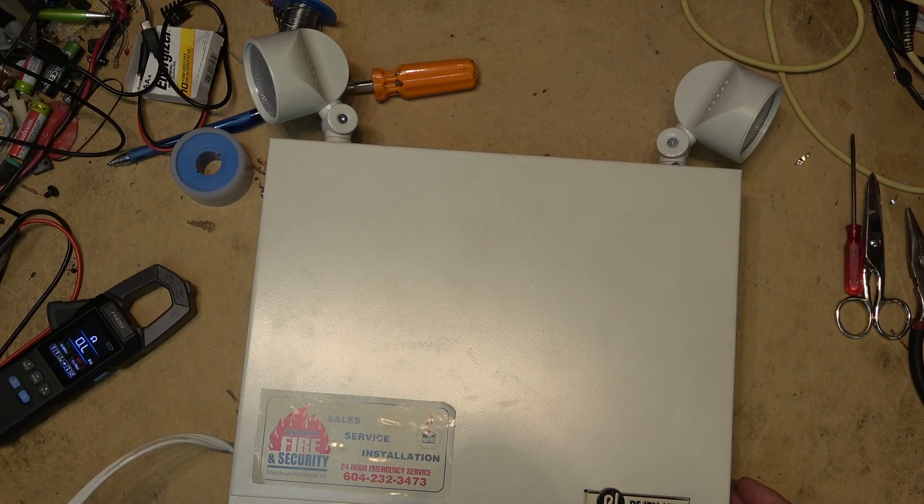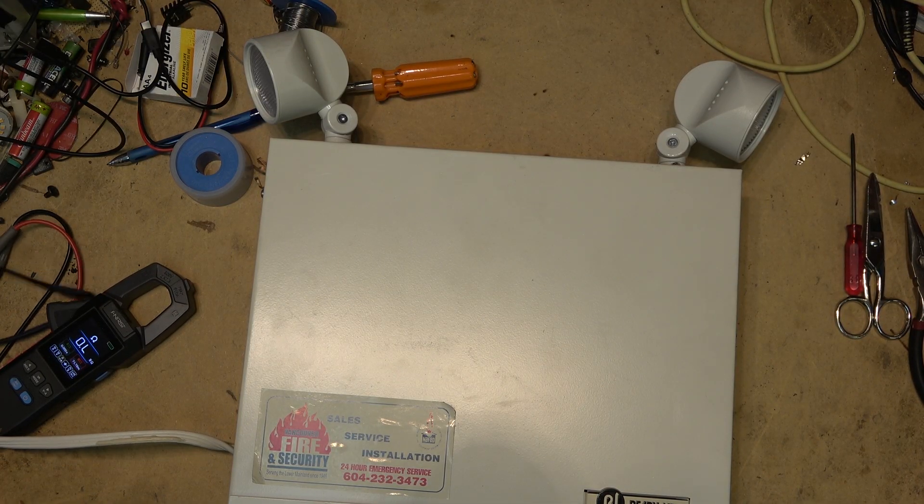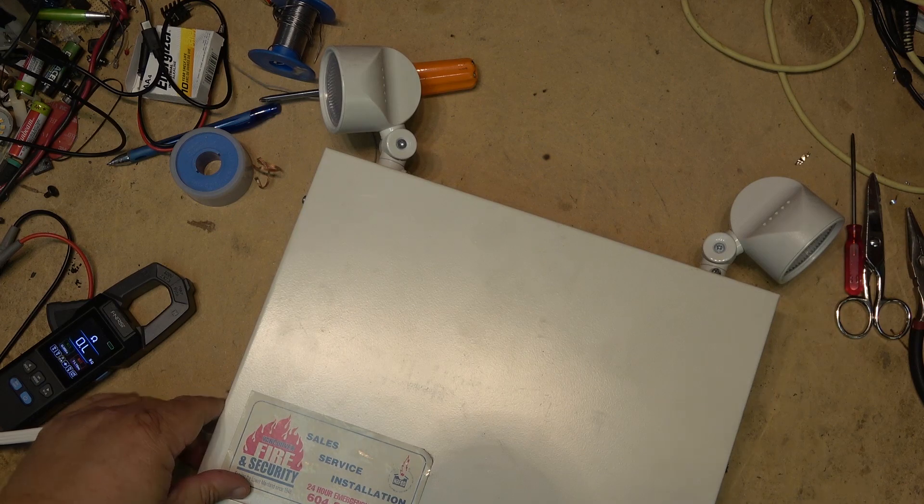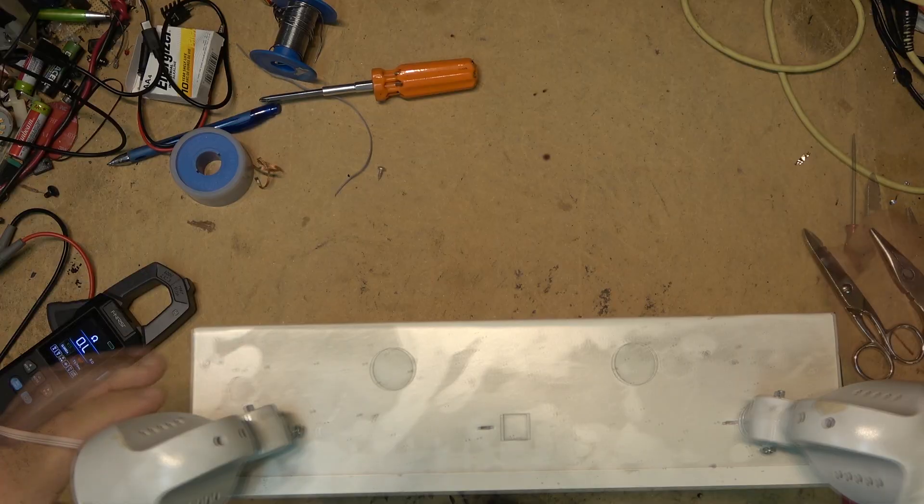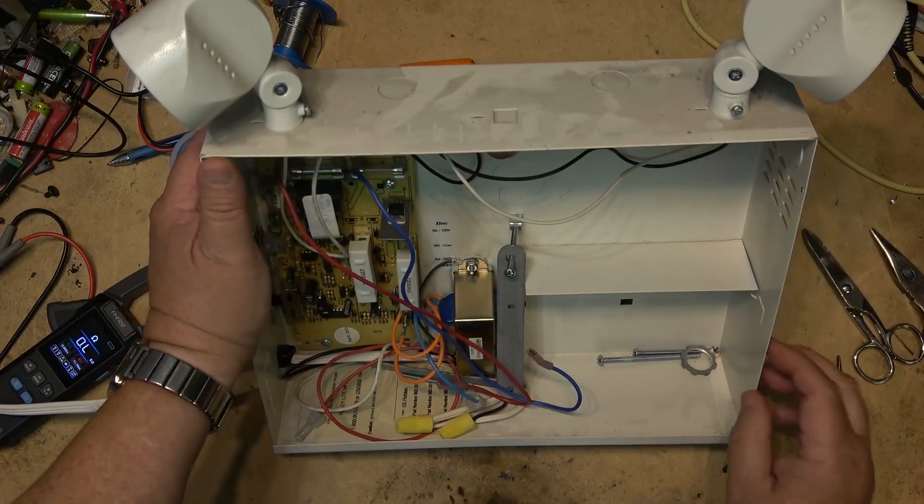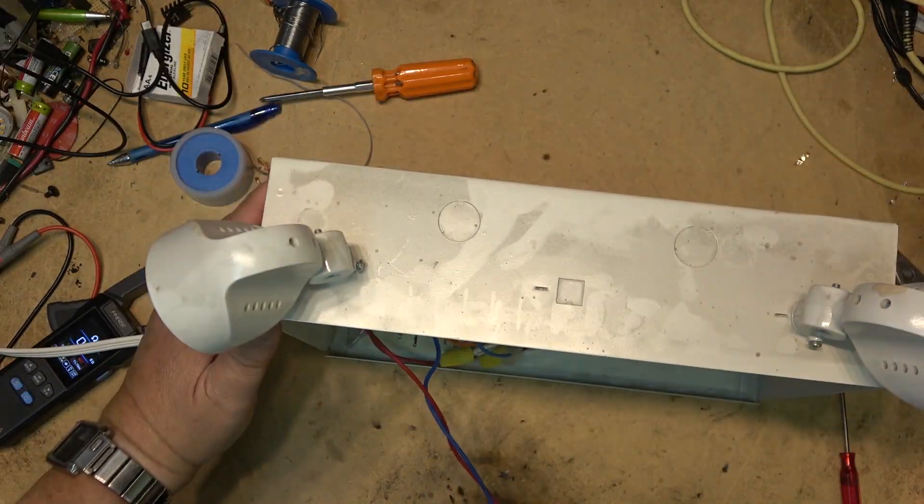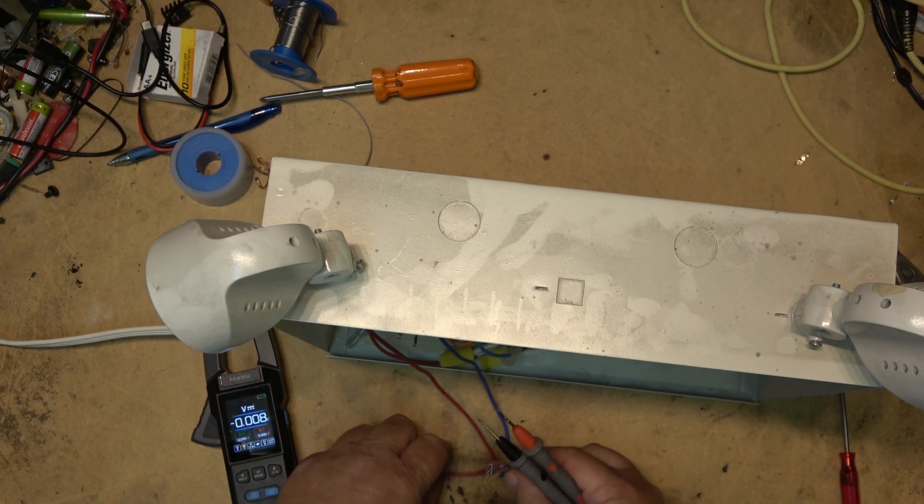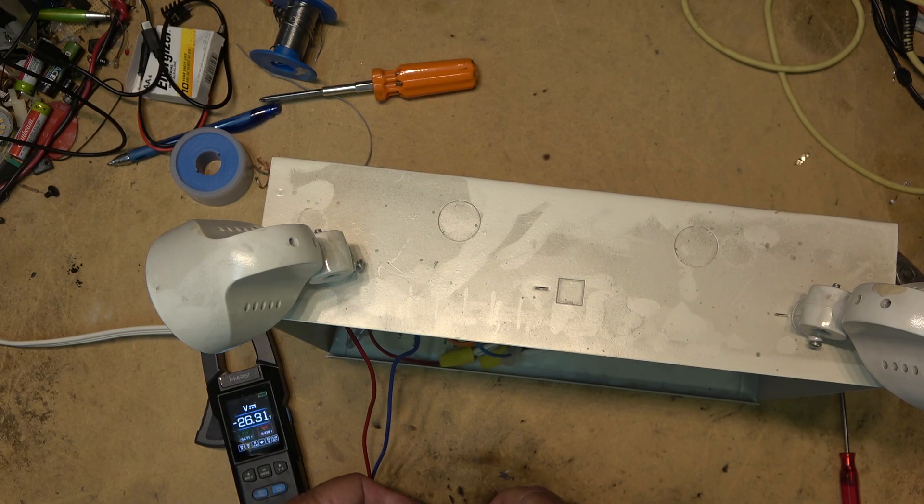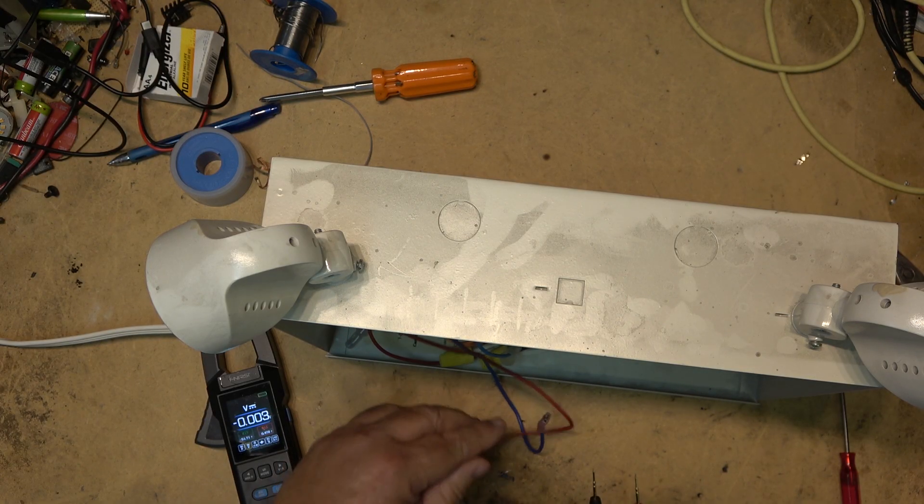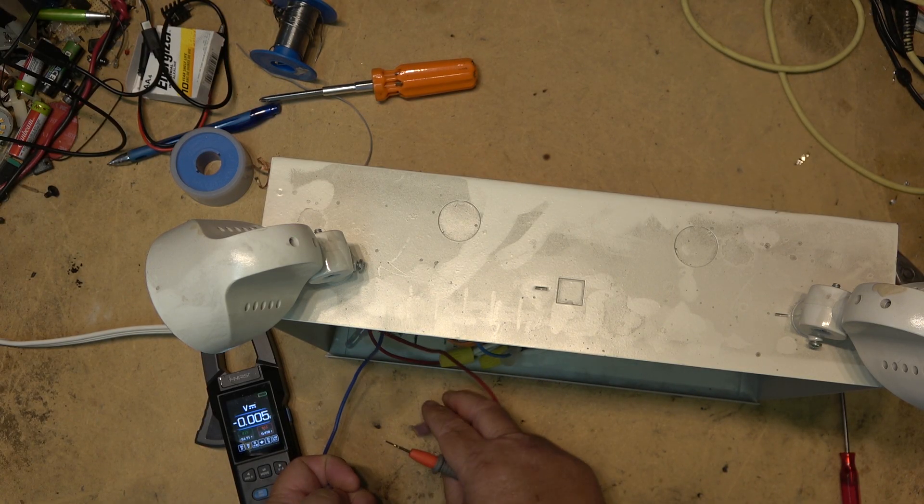Now the fellow that brought me this is an electrician. He was working in a building that this was not working in, and he took it out and brought it to me to see if he can figure out why it doesn't work. So it probably does not have a battery in it at the moment, which it doesn't. But that's okay, I have a battery that I can plug in here for testing because it's going to be 12 volts. We'll check and see if we've got power on the battery charging terminals. 19 volts, so it should charge. I'm going to grab a 12 volt battery.